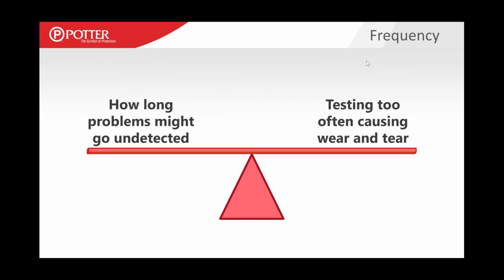The other piece that goes along with this: we've identified what the issues are that we want to look for in an inspection or a test, and then we apply this frequency, and we use the definition out of 25. The other piece in this conversation is the balance of trying to find that sweet spot between how long a problem might go undetected versus testing or inspecting so often that you cause a problem. Think about this in terms of a fire pump. We want to reduce the amount of time that a fire pump could potentially sit there and not be working, but we also don't want to test it so often that we wear it out. So could we test a fire pump every day? The answer is, of course, yes. But although it would reduce the amount of time a problem could go undetected, we would also wear out the fire pump that much sooner. So there's got to be a balance there.